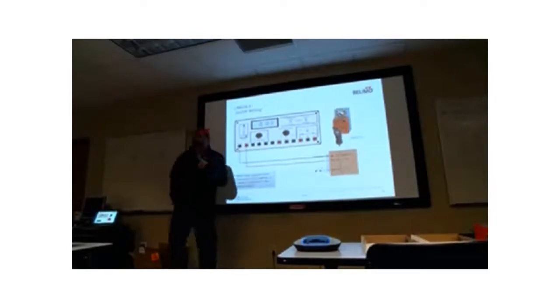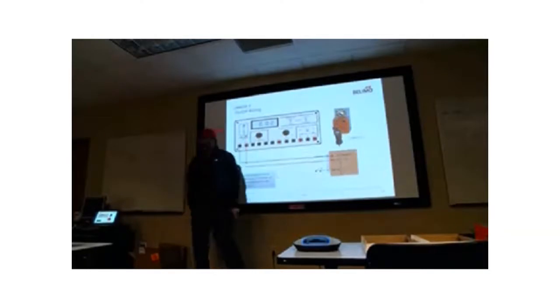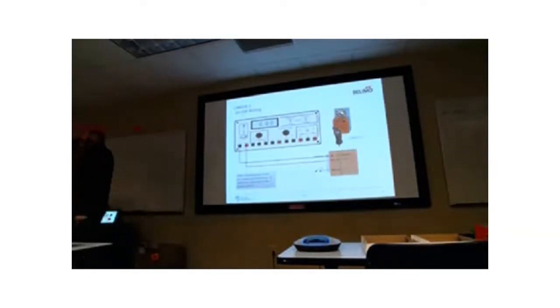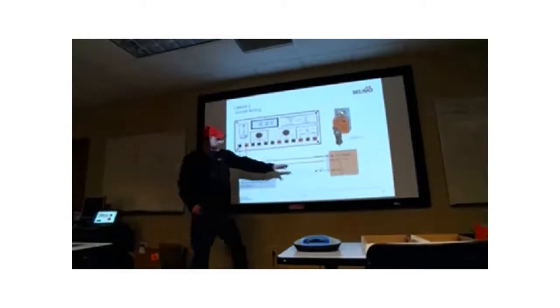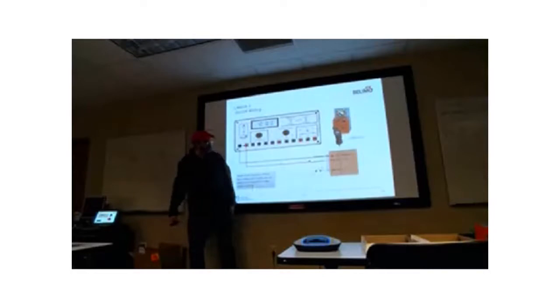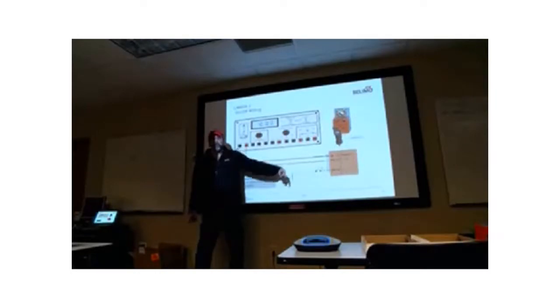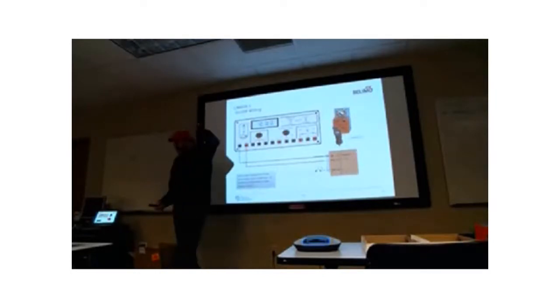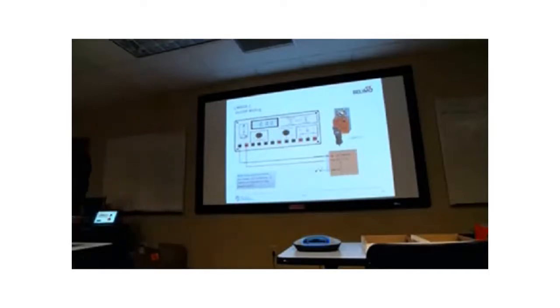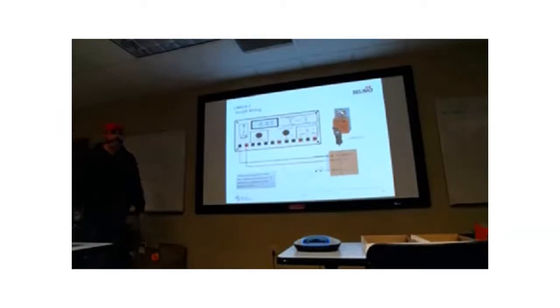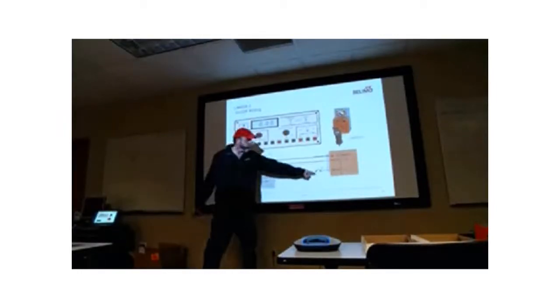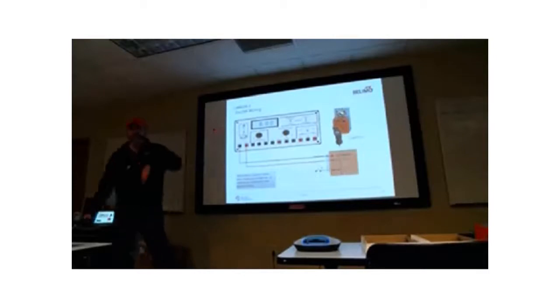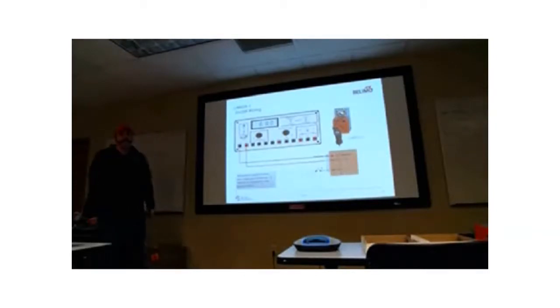So what you do in actuality, if you guys are wiring this, you would put your digital output in series with that white wire. And that's how you would get to position control. When this switch is open and the switch is in the 1 position, the actuator goes clockwise. When you close that switch, the actuator goes counterclockwise. Does that make sense? So that's your relay. Your digital output relay is in series with the white wire, and that's how you get to position control with 1 digital output.